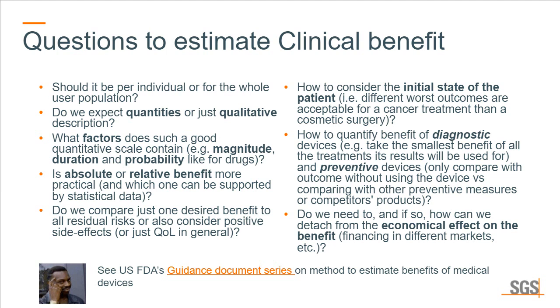So if you have, for example, a linear accelerator for radiotherapy treatment of cancer patients who already have cancer, then the risk of the linear accelerator causing more cancer is not as severe as, for example, if you have an acne treatment laser device, which is to treat skin defects or skin conditions in an otherwise healthy patient. We would definitely not accept an acne laser treatment to cause cancer and melanoma in the patient. So that is maybe just to illustrate the concept that the risk benefit should also take into consideration the benefit.